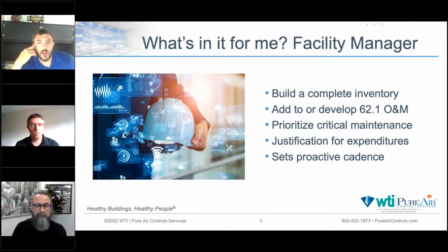And so upon the inspection, our inspector immediately told the facilities team so they could get that final filter changed. And it just had gone unnoticed from just lack of inspections by that particular healthcare facility.